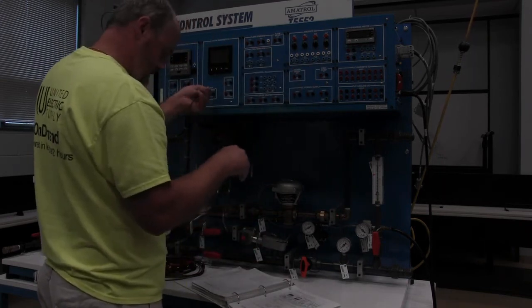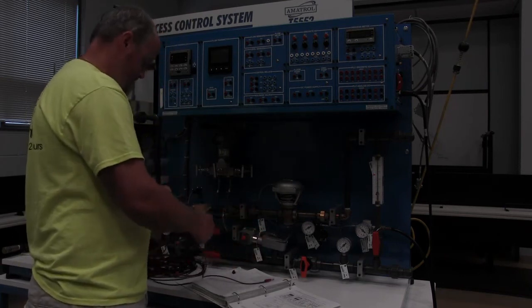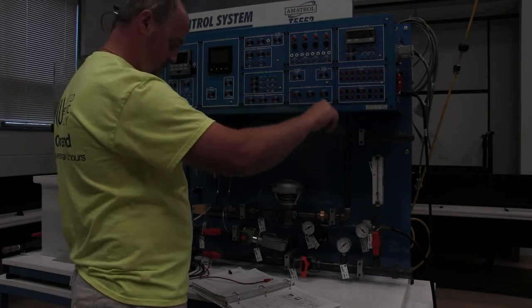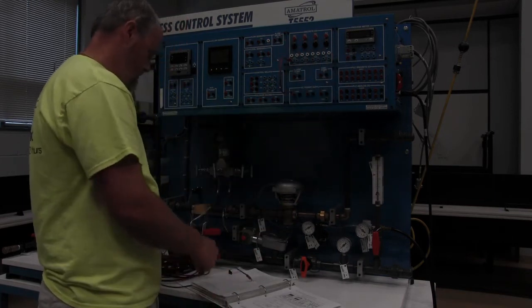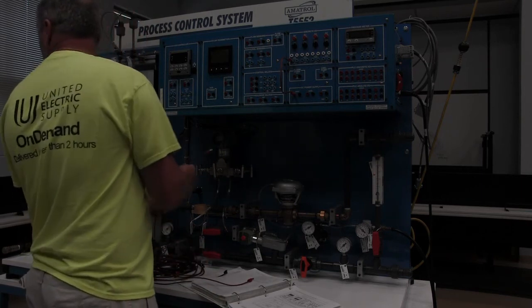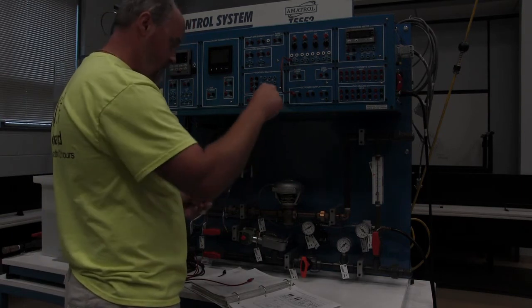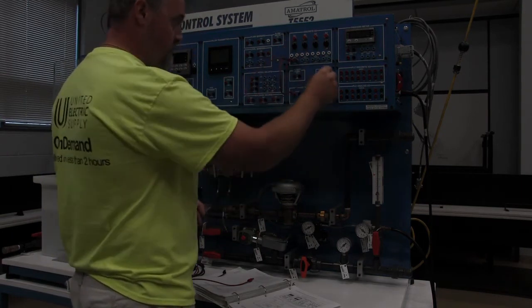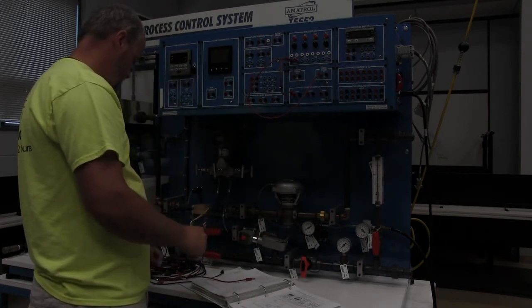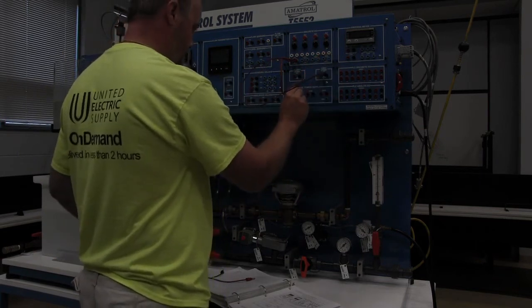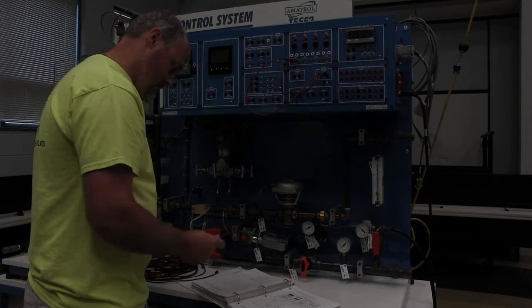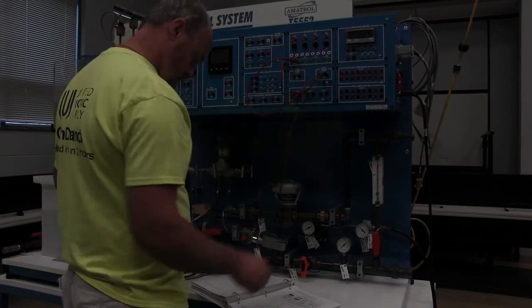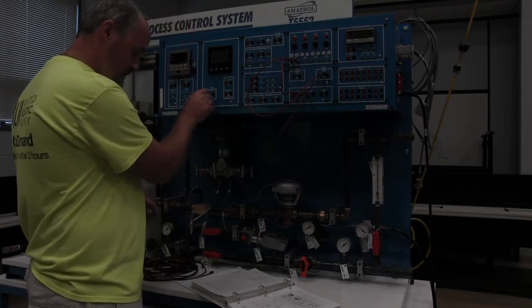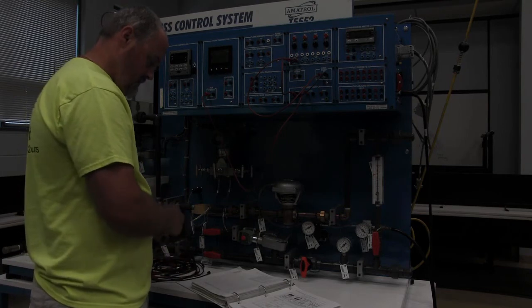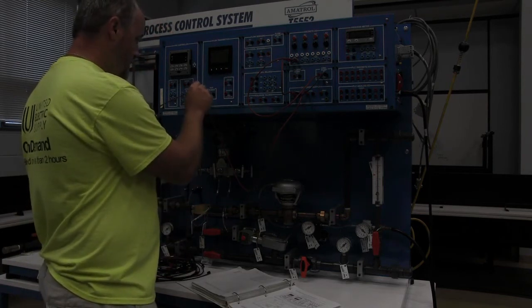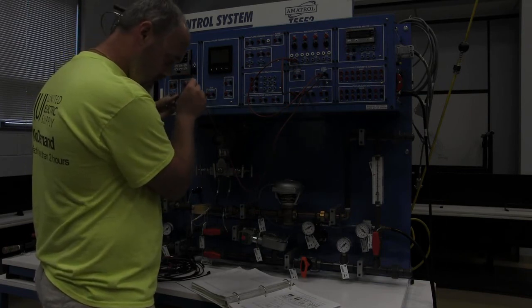Let's see here, I'm going to start from the beginning. We're going to go from 24 volts to selector switch 1. From selector switch 1 to the circulator pump. The circulator pump back to the negative. Then we are going to go from the 24 volts to the flow transmitter auxiliary power. From the auxiliary power to the flow transmitter output AI1.